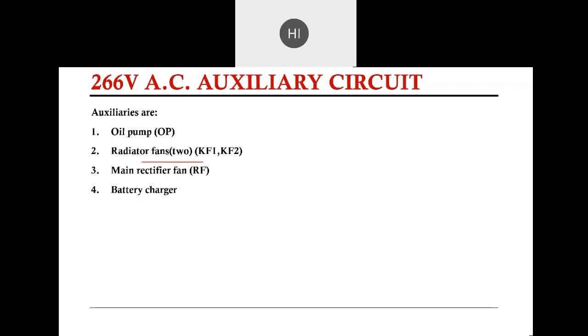And the details about this thing, the oil pump - this oil pump is provided to circulate transformer oil to keep it cool. The motor is a 4-pole squirrel cage induction motor, 1.5 HP rating, runs at around 240 volt AC, 50 hertz, and this is basically the rating, pump capacity and head. This is the oil pump.